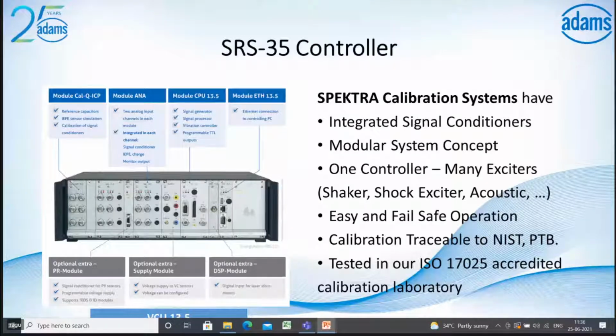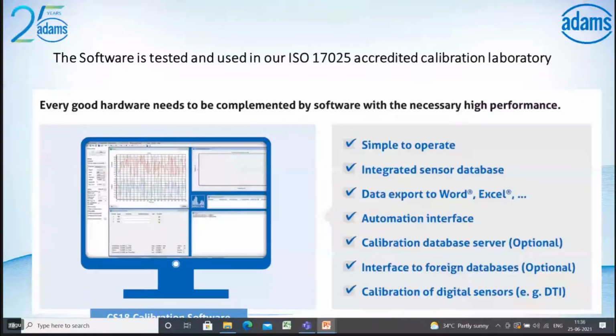And the software, it's a CS18, it's a calibration software. So every hardware, every good hardware needs to be complemented by the software. So with the high performance, it should be easy to operate, and it has the integrated sensor database, and you can export the data to Word or Excel, and it has the automation interface, and they'll be giving optionally a calibration database server, and optionally a foreign database to interface with the system, and the calibration of digital sensors can also be done.